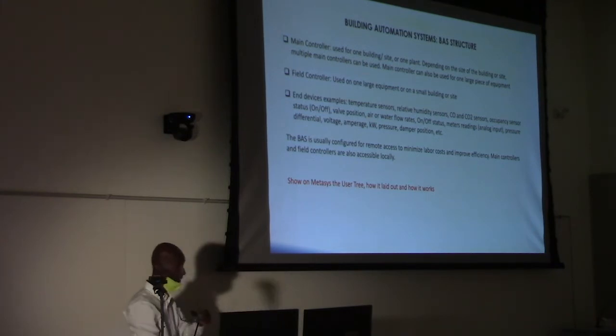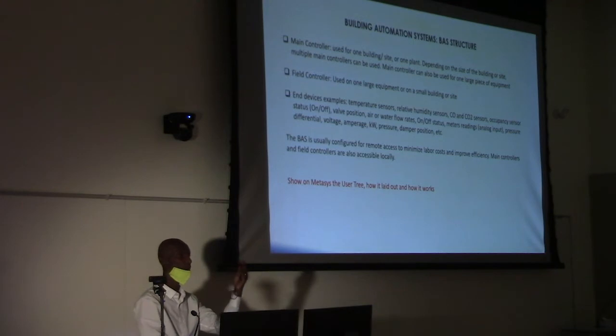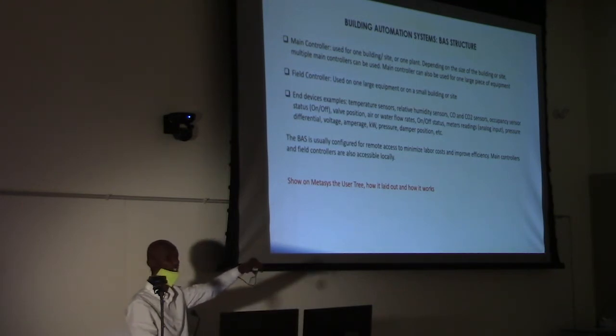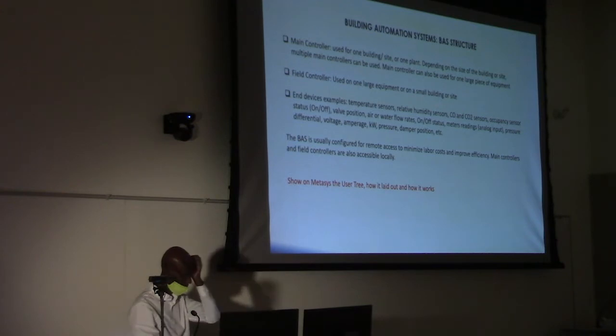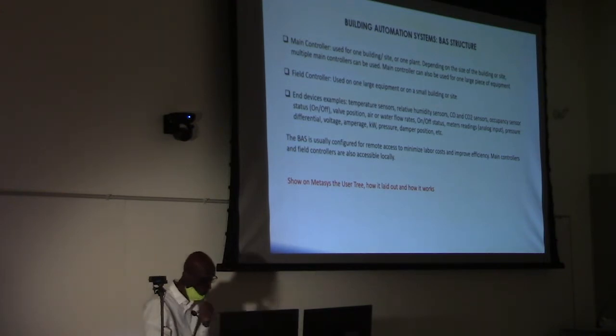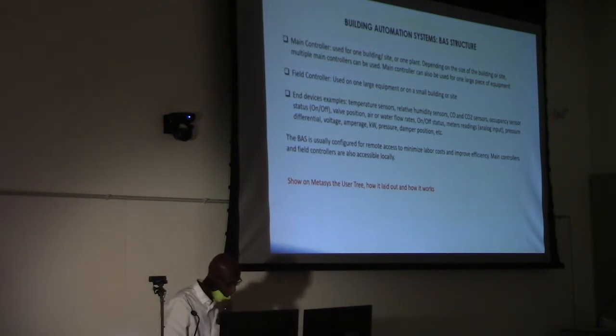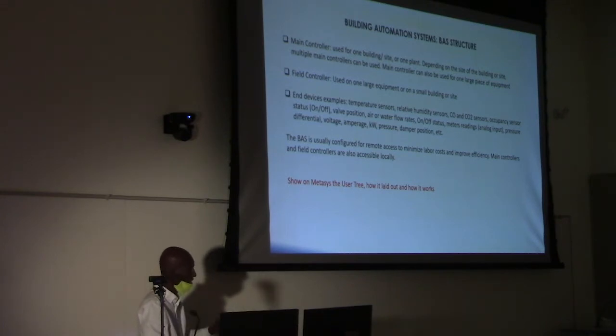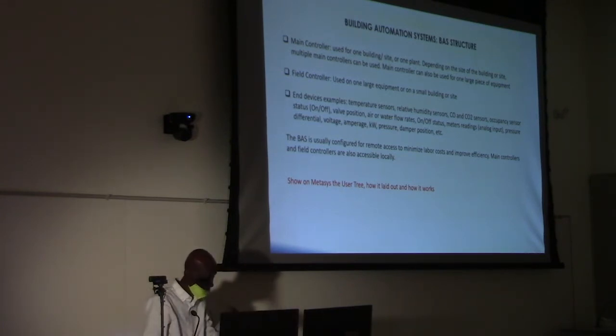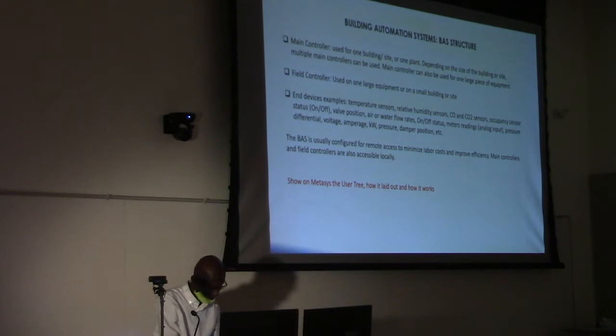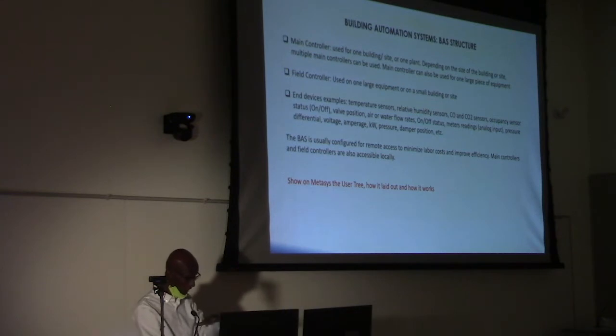Valve position, because you may have a chilled water or hot water, so you want to modulate the valve position to control your temperature. Air flow rate or water flow rate, on-off status of equipment, meter readings, pressure differential, voltage, amperage, kW, pressure, damper positions, and so on. So the building automation system is usually configured for remote access to minimize labor cost, we talked about it, and improve efficiency. Main controllers and field controllers are also accessible locally or remotely.